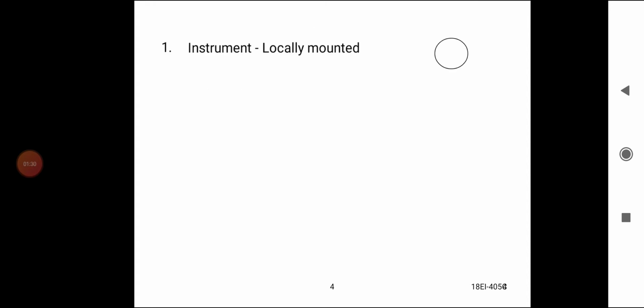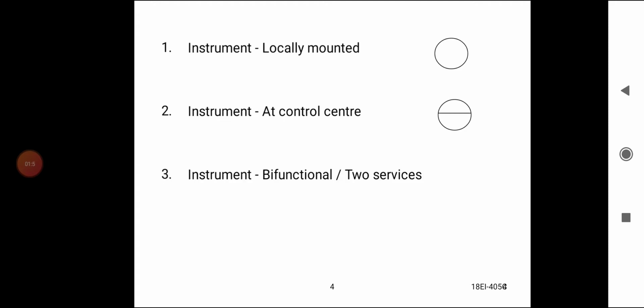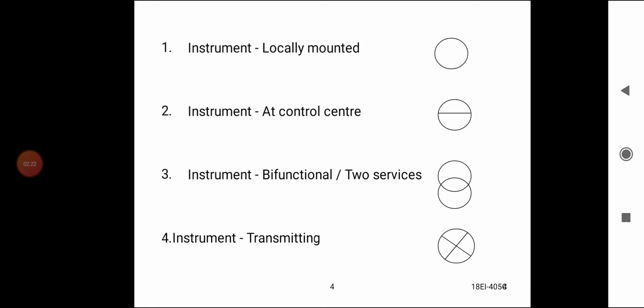1. Instrument locally mounted: simply a circle. If it is a locally mounted device, it is a circle. Second, instrument at control center: a circle with a line in the middle, two half circles. That indicates the instrument located at control center. The instrument is bifunctional, or has two services, when the two circles are sharing. Instrument transmitting: a cross marking in the circle represents a transmitting device.